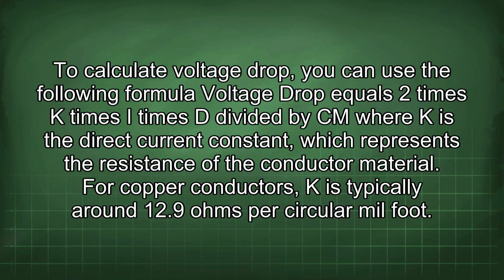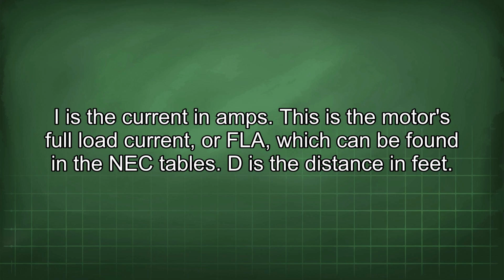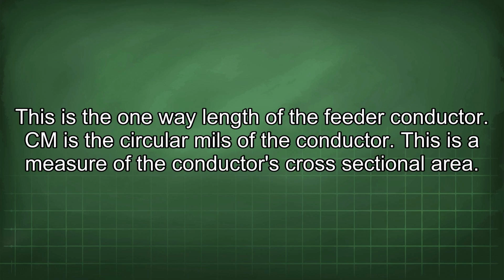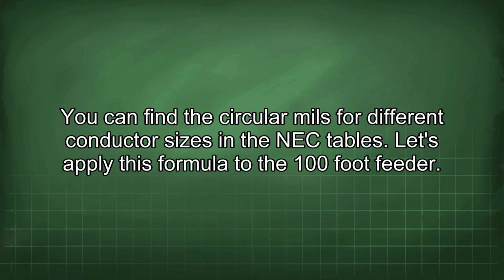the source. To calculate voltage drop, you can use the following formula: voltage drop equals 2 times K times I times D divided by Cm, where K is the direct current constant, which represents the resistance of the conductor material. For copper conductors, K is typically around 12.9 ohms per circular mil-foot. I is the current in amps. This is the motor's full load current, or FLA, which can be found in the NEC tables. D is the distance in feet. This is the one-way length of the feeder conductor. Cm is the circular mils of the conductor. This is a measure of the conductor's cross-sectional area. You can find the circular mils for different conductor sizes in the NEC tables.